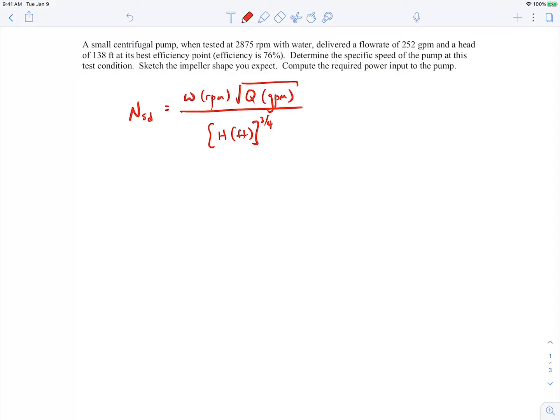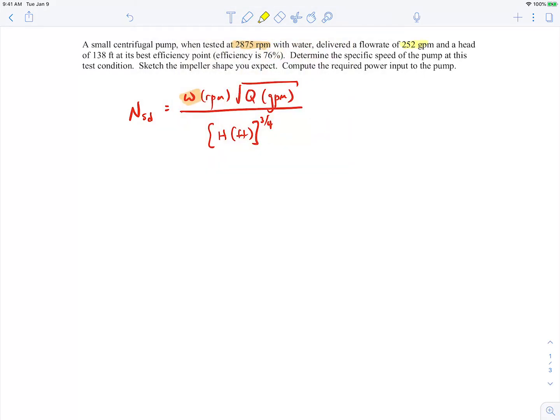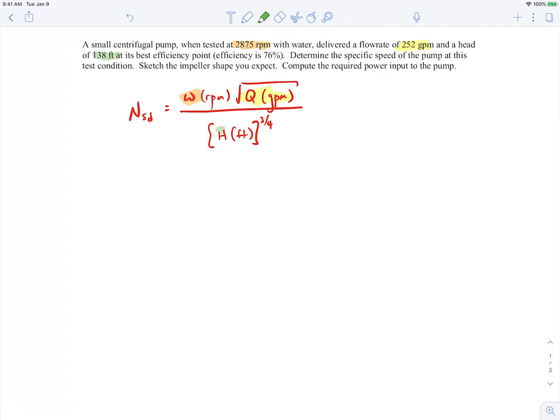We can go ahead and plug in the values here. We're given the rotational speed in RPM, that's this one. We're given the flow rate, that's this one, in the correct units. And then we're also given the head rise in the correct units, so that's that one. When you plug the numbers in, you'll get that the dimensional specific speed is 1,130 RPM gallons per minute to the one-half feet to the minus three-quarters. It's an unusual set of units.